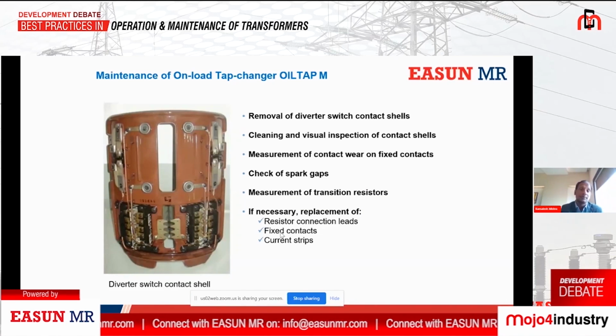Finally, in the diverter, you have basically a transition resistance. You can see there are 4 wires coming. There you have to check the resistance also. That is called transition resistance. You have to check the connection, whether the connections are tight or not. The sparking gap is there. You can see the sparking gap, whether I could point here. You have to check this also. What is the distance, whether maintained or not.